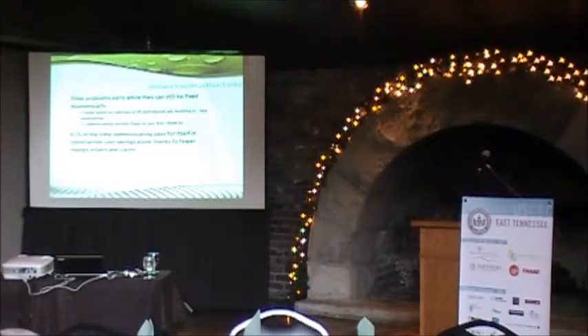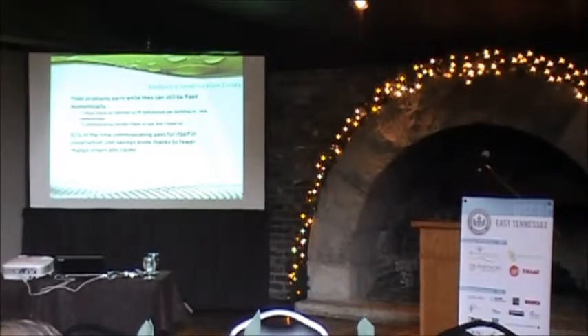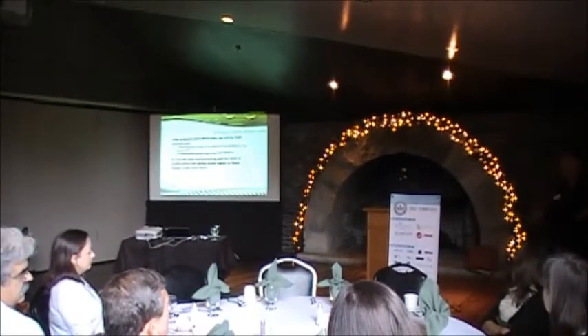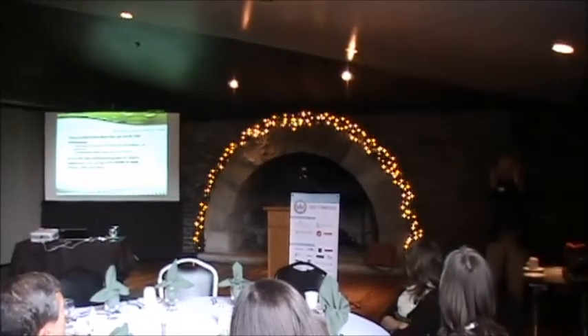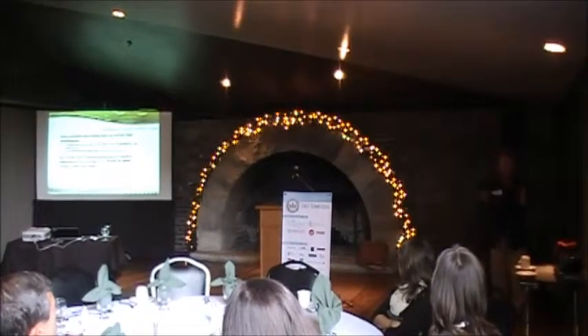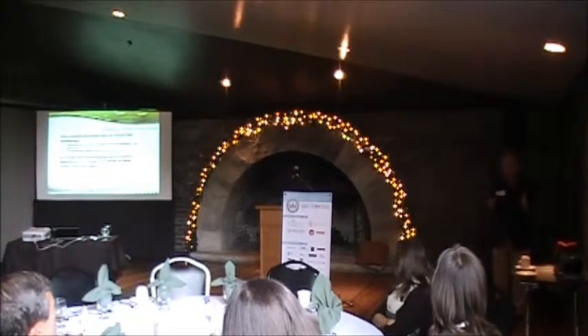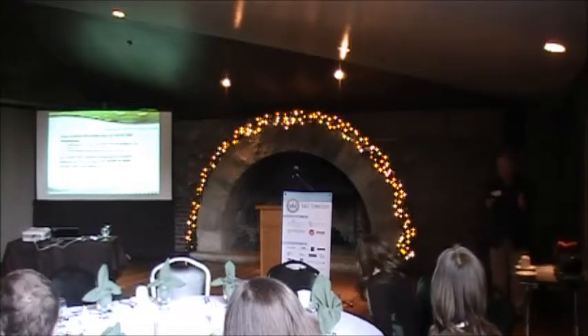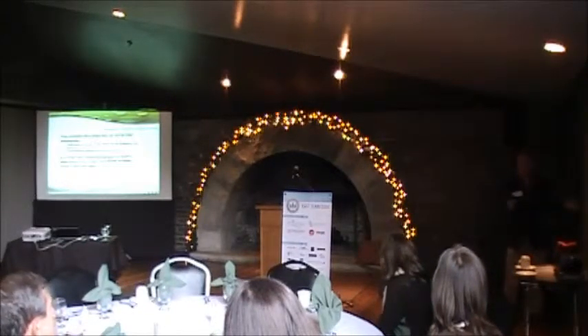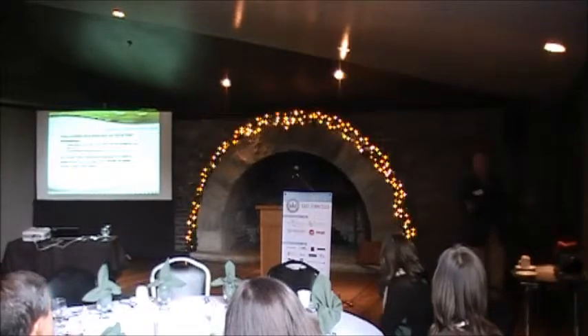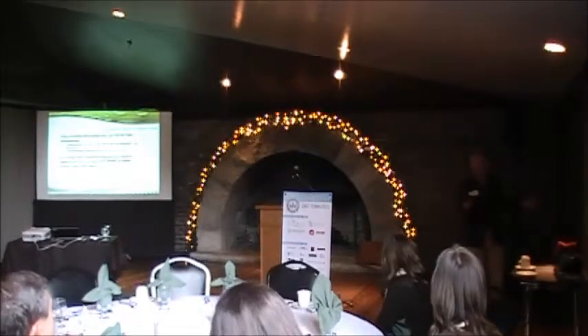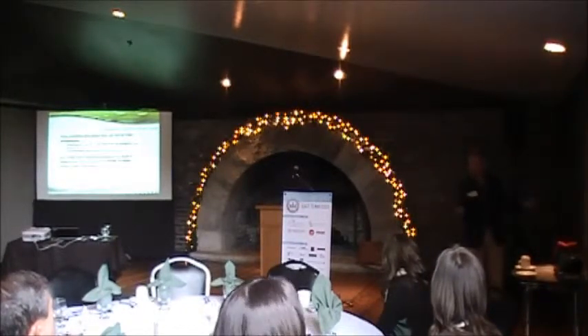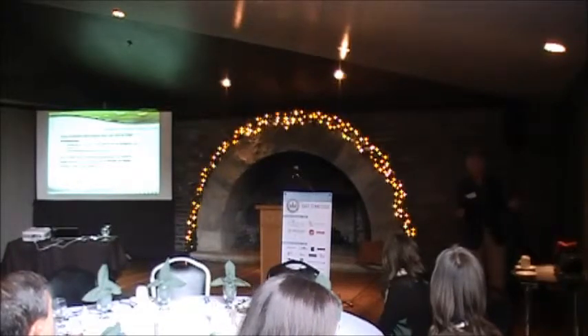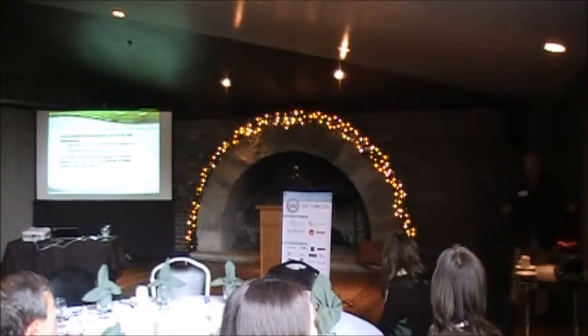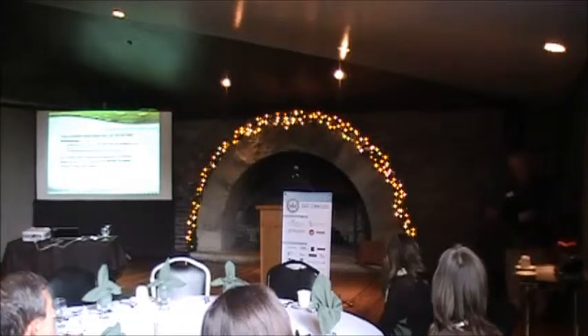We saw they have VAV units, variable air volume control units, and this run of ductwork going along the wall, and the VAV unit has an access hatch for maintenance. It's supposed to swing open so somebody can get in there and change the motor or do something, but it was so close that you couldn't maintain anything.